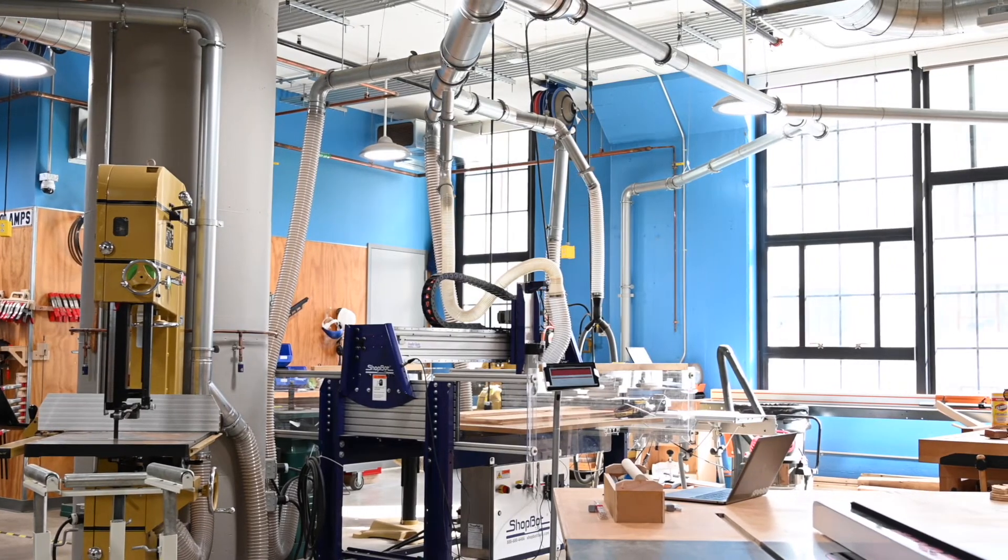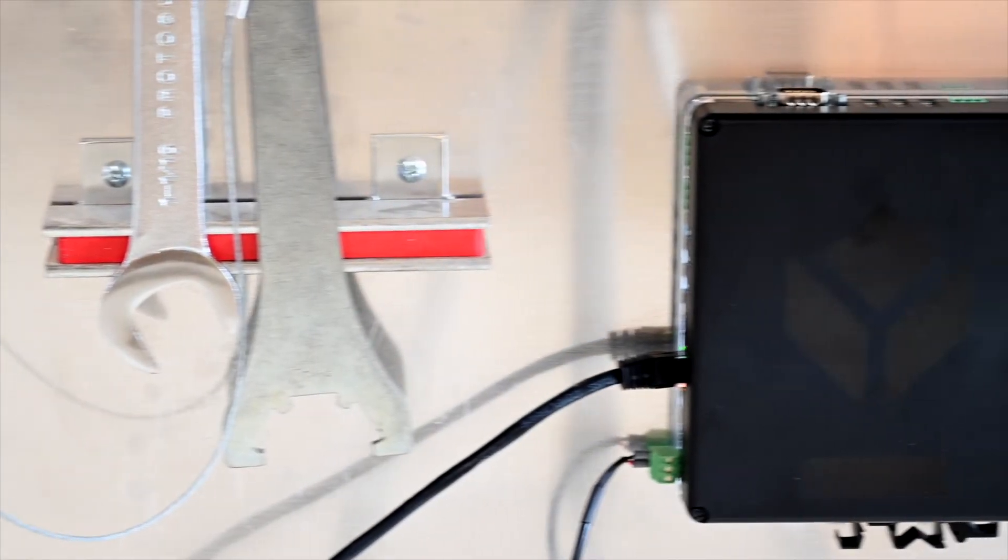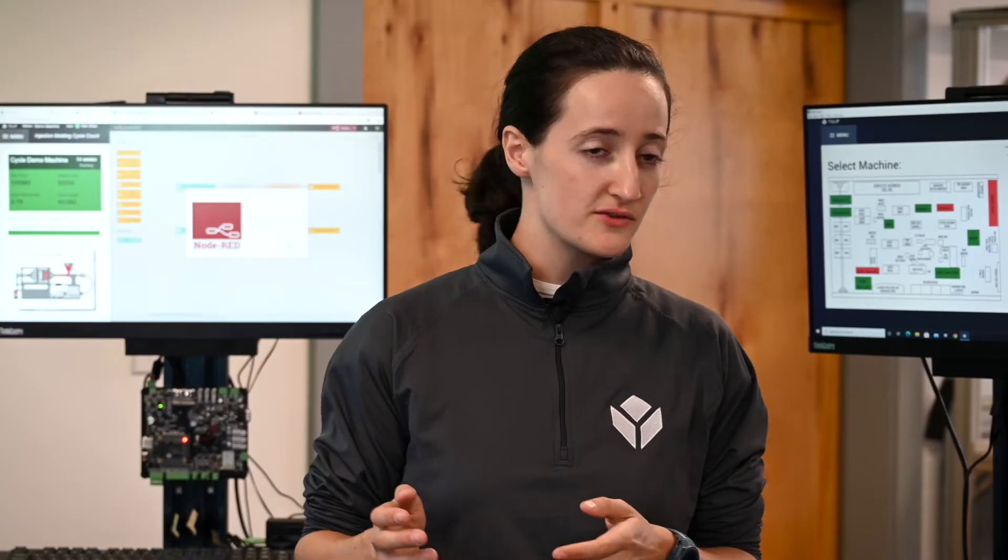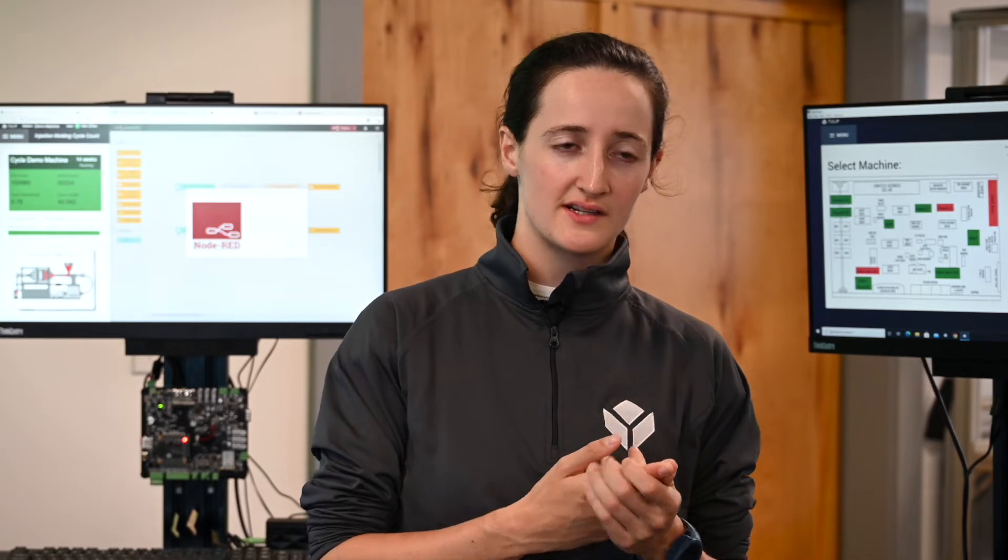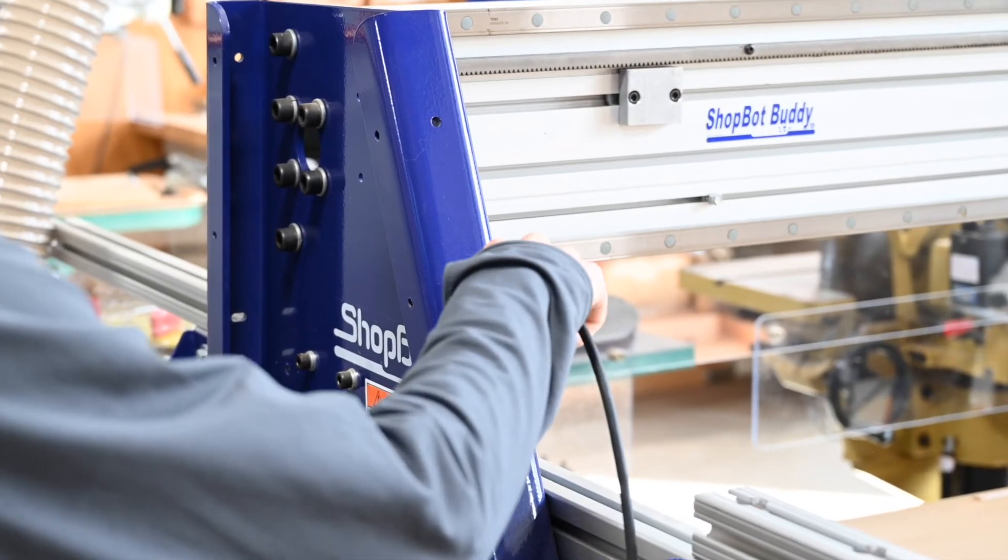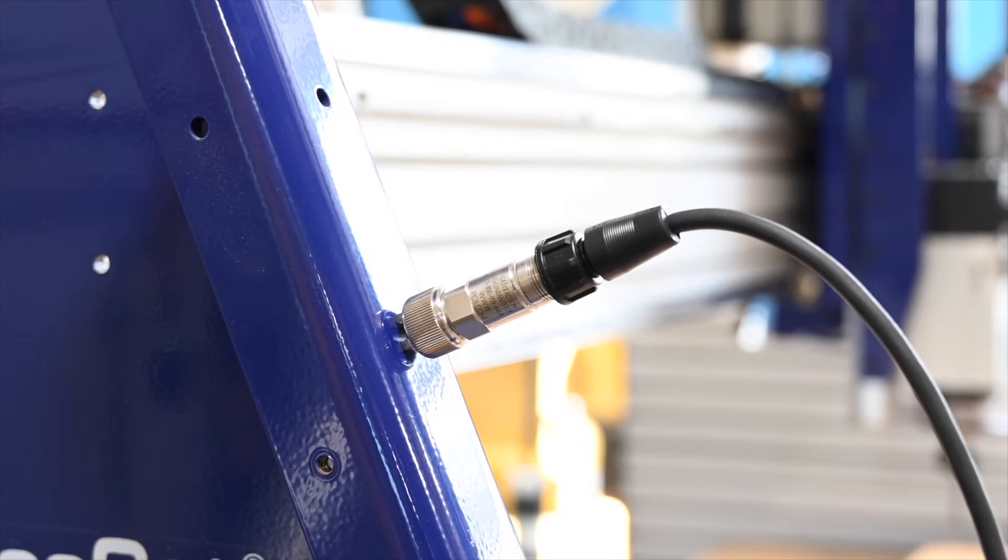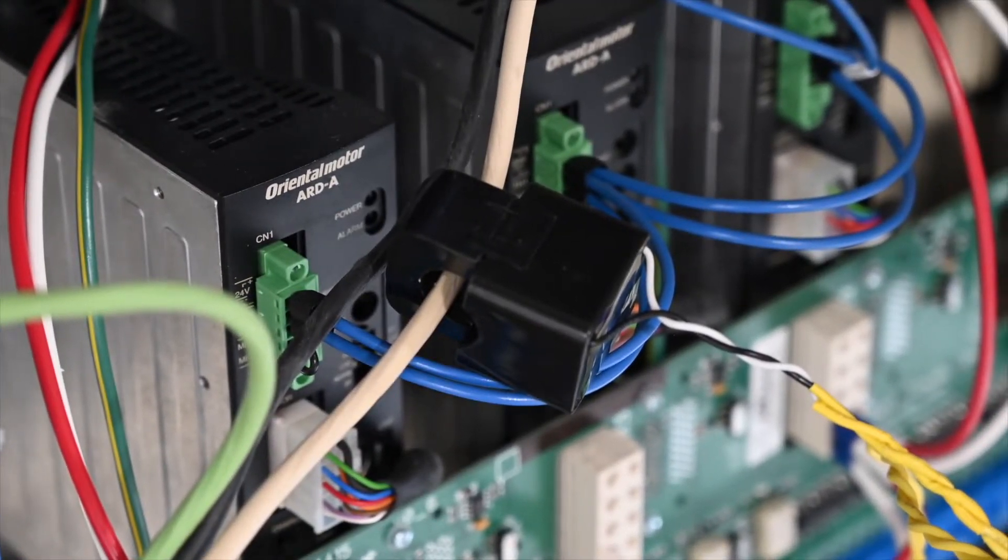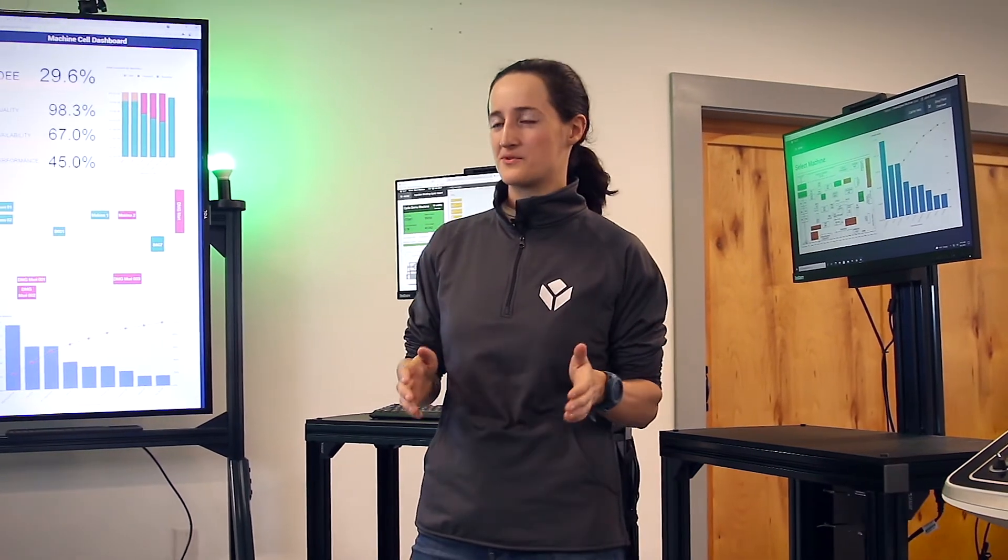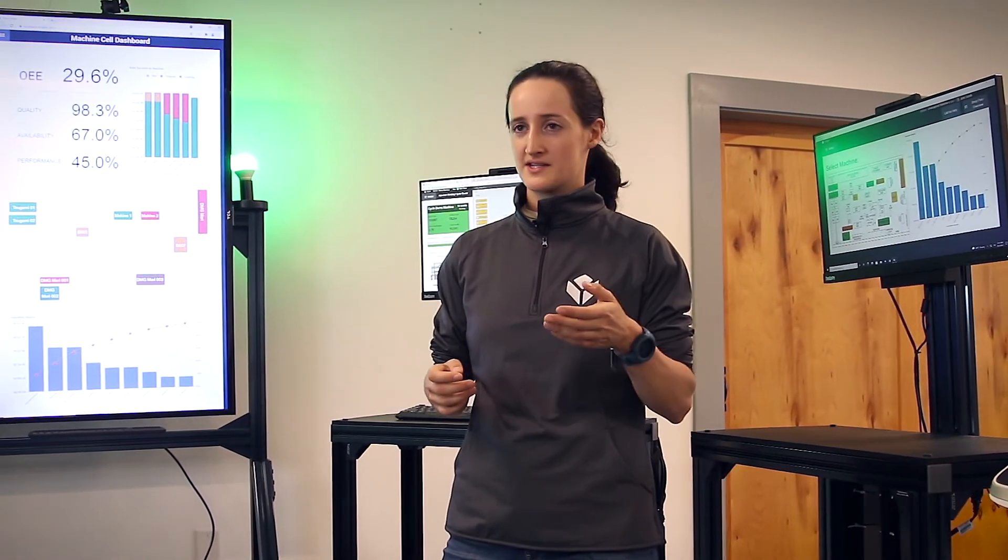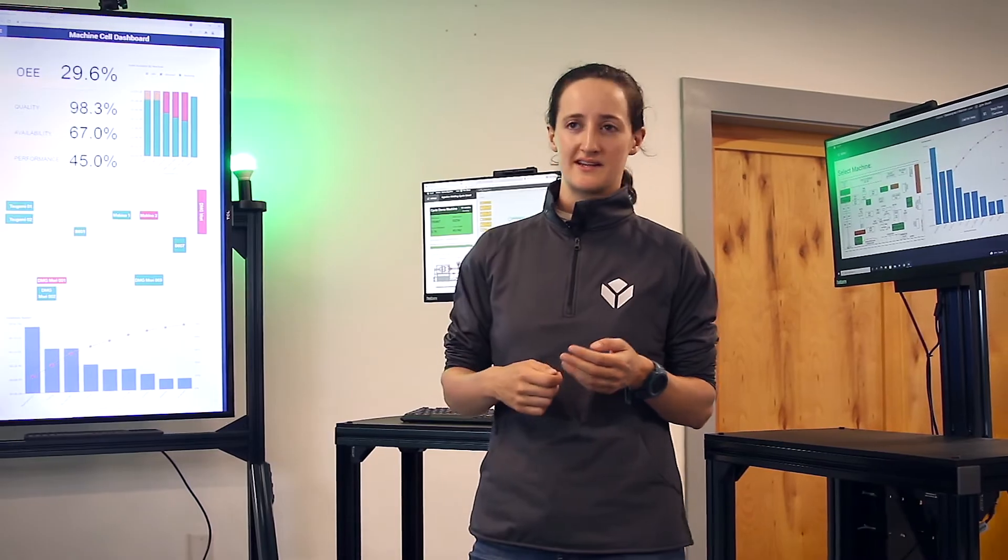At Autodesk we were testing using the Edge.io to monitor a CNC mill, and to do this we were using both a vibration sensor and a current clamp. The vibration sensor on the chassis of the CNC mill and the current clamp was hooked up to the power supply. The Edge.io is designed specifically to work with these low-cost off-the-shelf sensors. You can buy the sensor and plug it directly into the Edge.io.